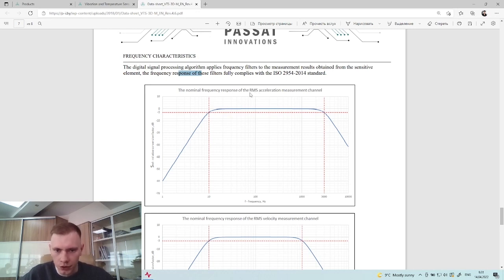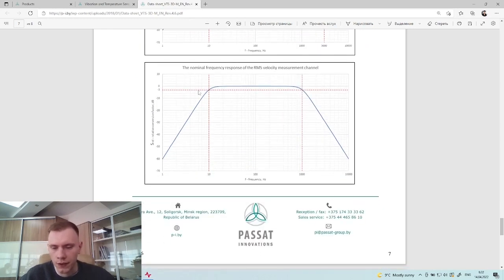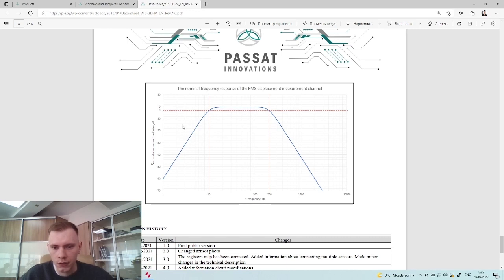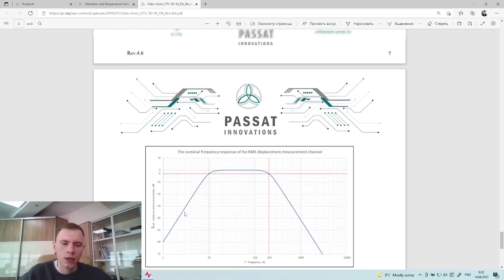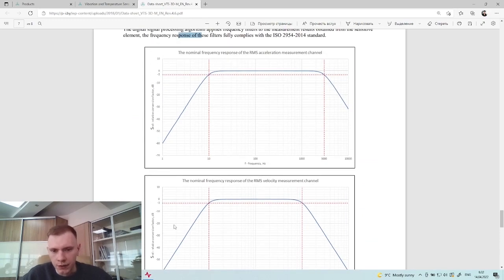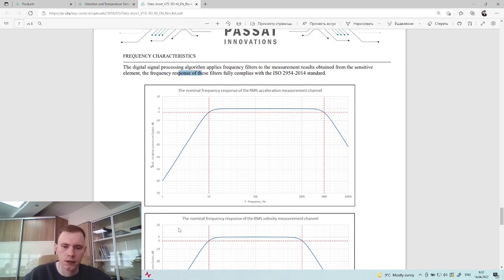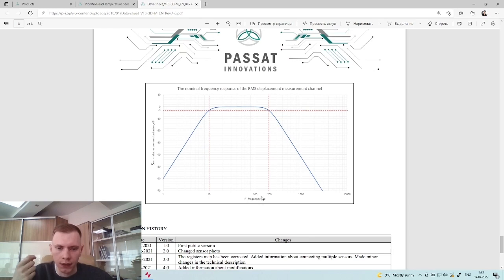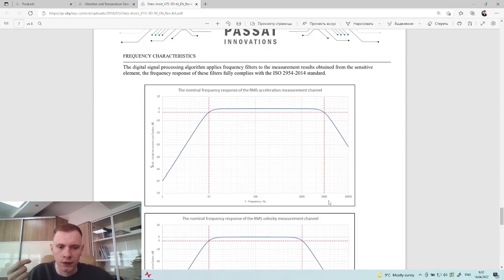So for acceleration we have -3 decibels at 10 and at 3000 hertz. For velocity we have -3 decibels at 10 and 1 kilohertz. And for displacement we have -3 decibels at 10 and at 200 hertz. So we will see it in action. I will put some magnitude on our vibration exciter. Firstly, I will put it at the calibration frequency 80 Hz, and to see the difference compared to this calibration frequency, after that I will put 10 Hz, and from lowest to highest, 200 Hz, 1 kilohertz and 3 kilohertz.